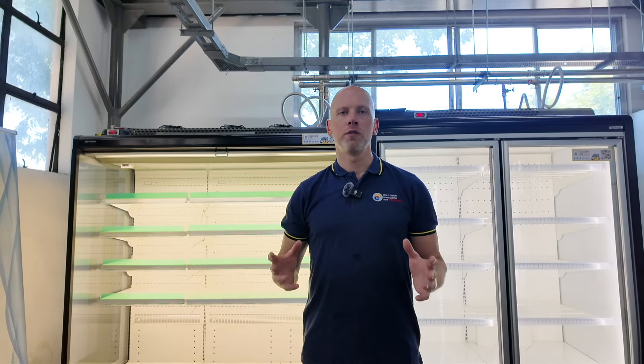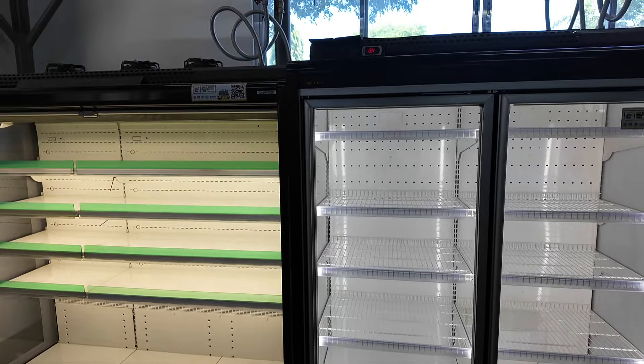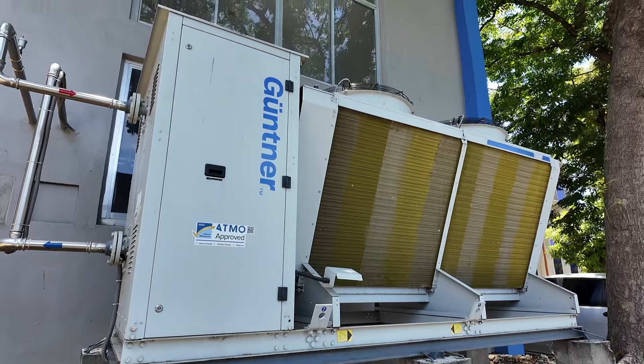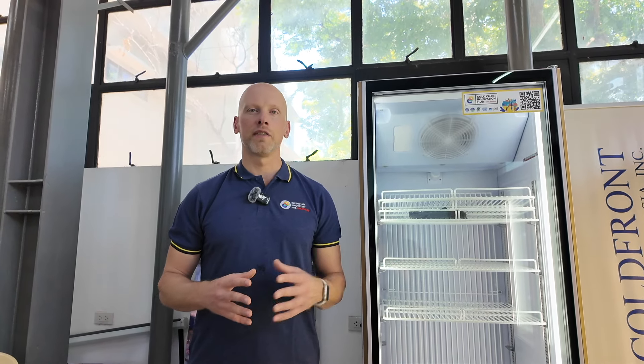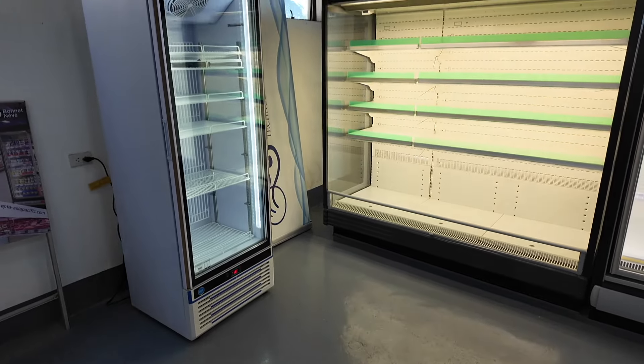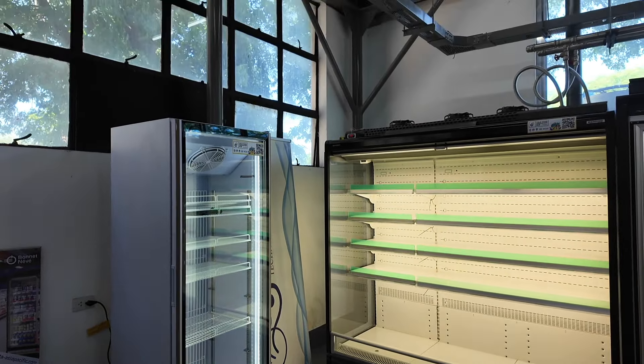Another example of the food retail solutions is behind me — showcases contributed from AHT. This is the first configuration of a so-called water loop, or hydro loop system, that rejects heat from the plug-in R290 cabinets outside of the building, where the dry-cooler pump station is located. R290 and isobutane hydrocarbons have been used for chest freezers as well as vertical cabinets. We also have a contribution from EPTA — two cabinets donated and contributed to the project here at the Hub.